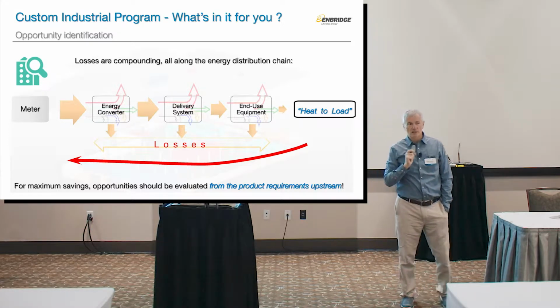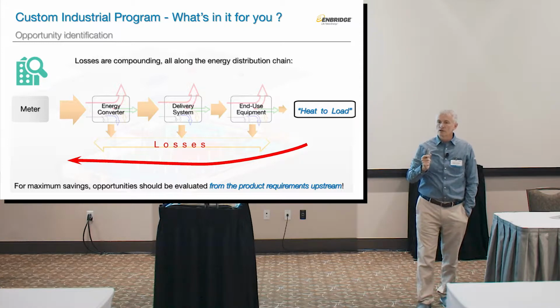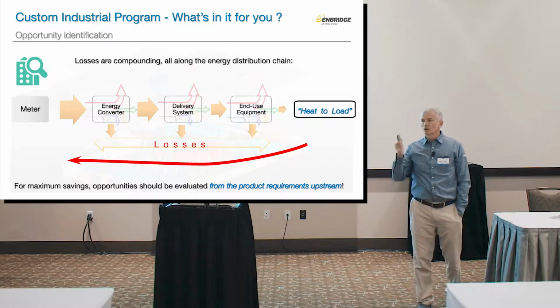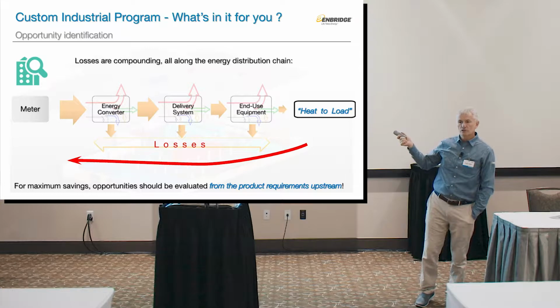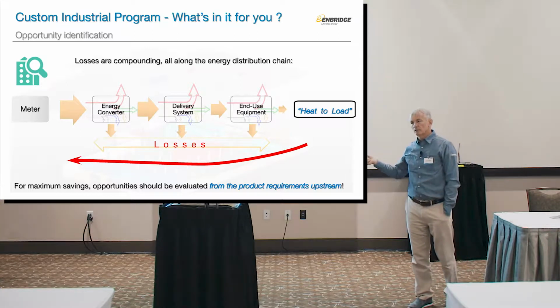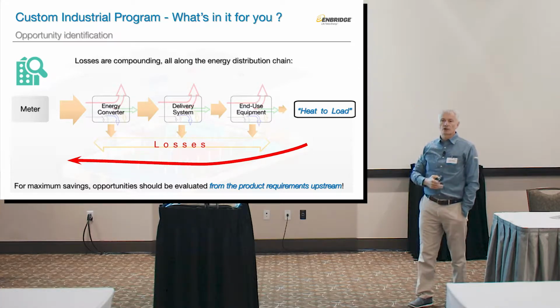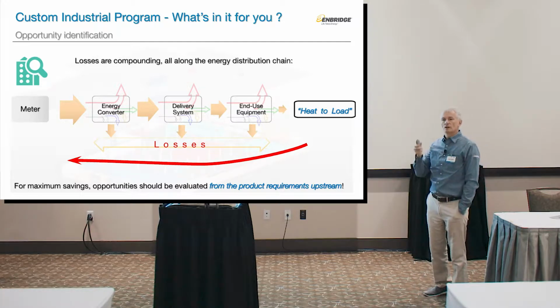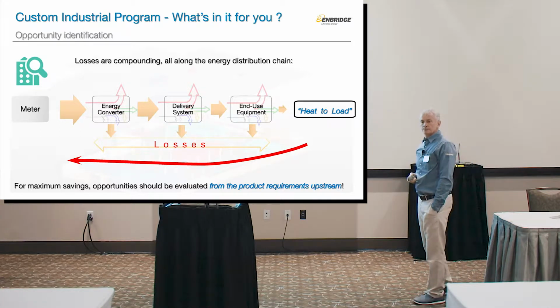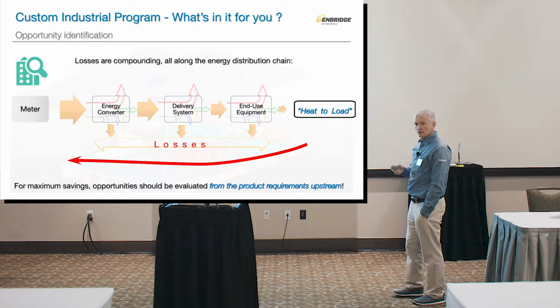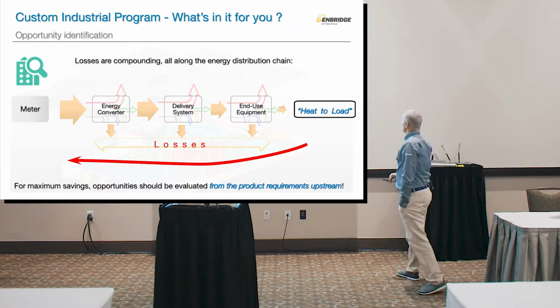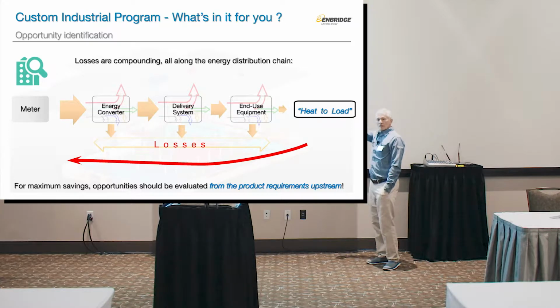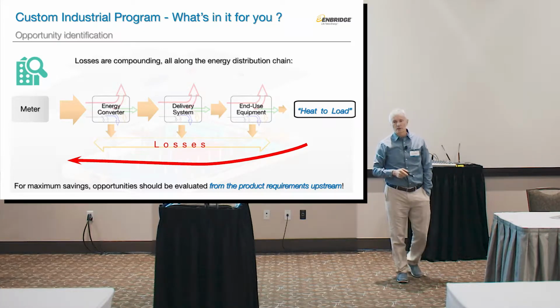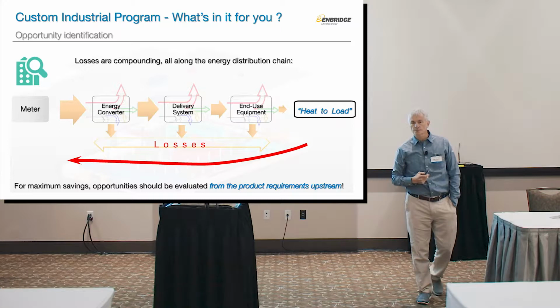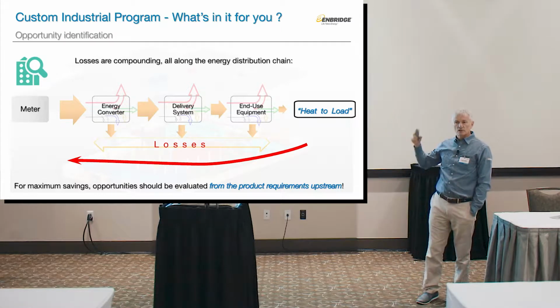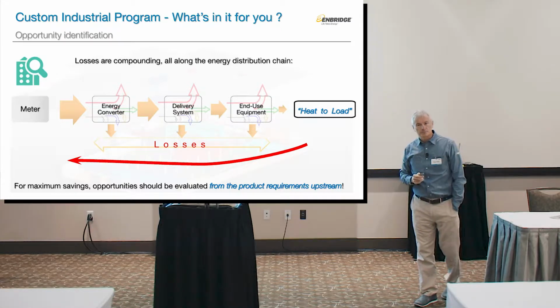And this isn't just natural gas equipment. Air compressors: 80 to 85% of the kilowatt hours you put into an air compressor is waste heat. You get nothing out of it. I don't care if you have a VFD, I don't care what you do, you will lose 85%. So out of 100 kilowatts, you only get 15 kilowatts of useful output, and of that, you waste 7.5 kilowatts on leaks. That happens with boilers, that happens with all sorts of equipment.